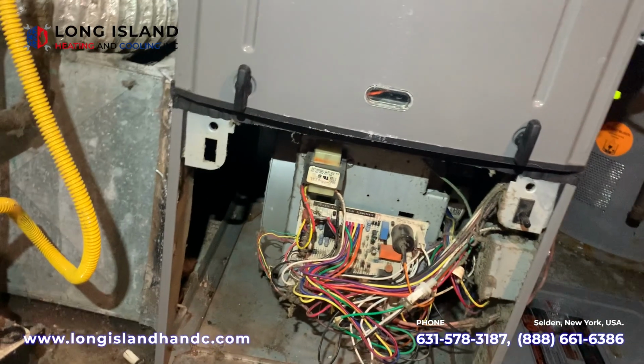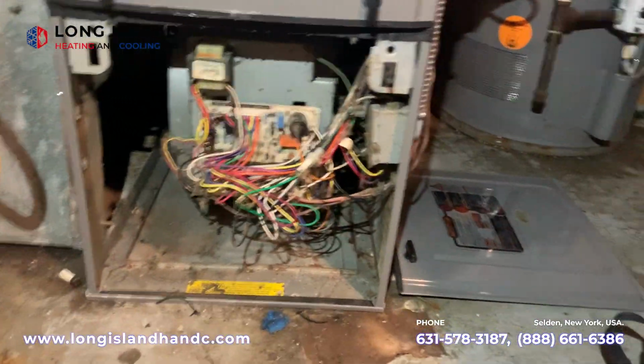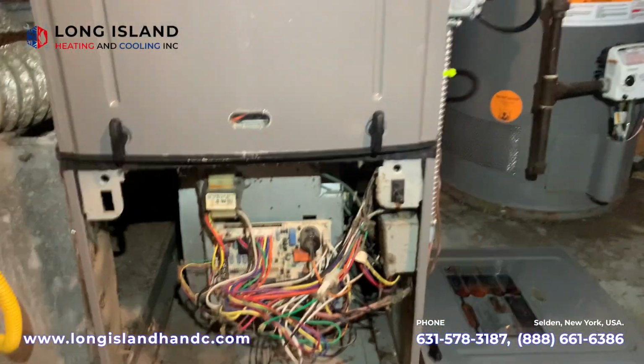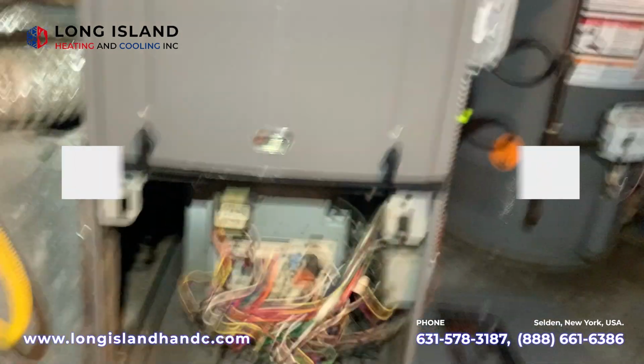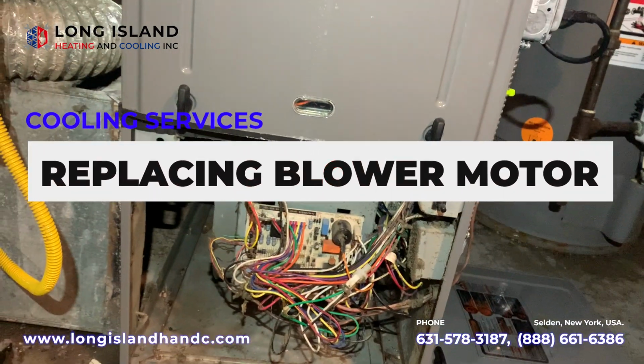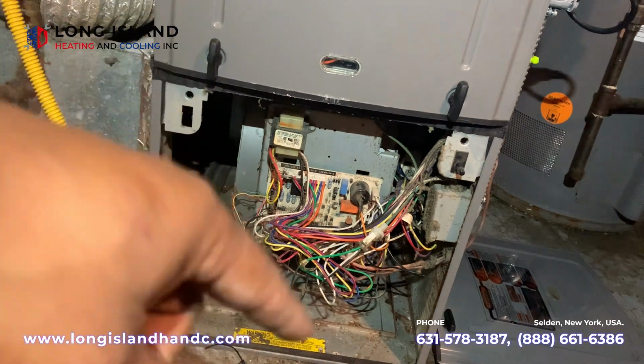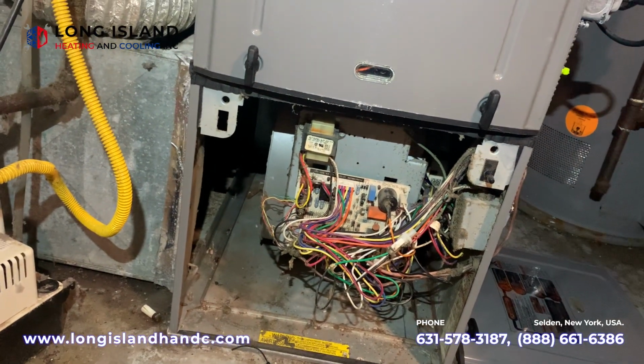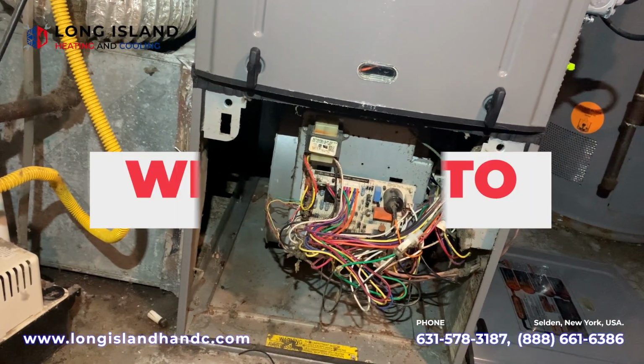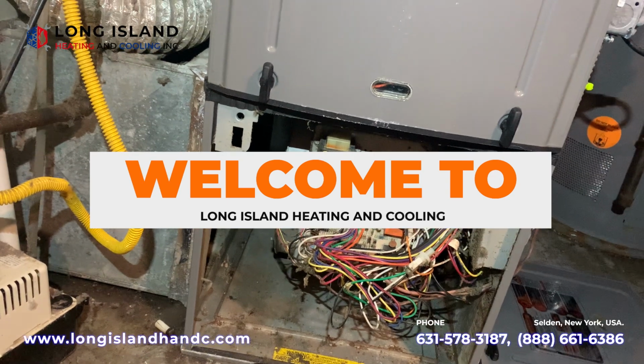I'm working on one of the gas furnace units. I came in 2 days ago, troubleshot this unit, and found out the blower motor is bad. The blower motor is under warranty, so getting this motor took me 2 days.